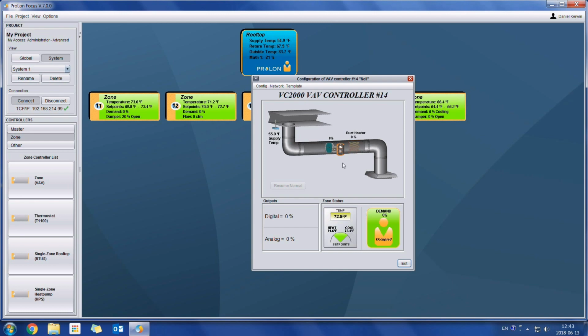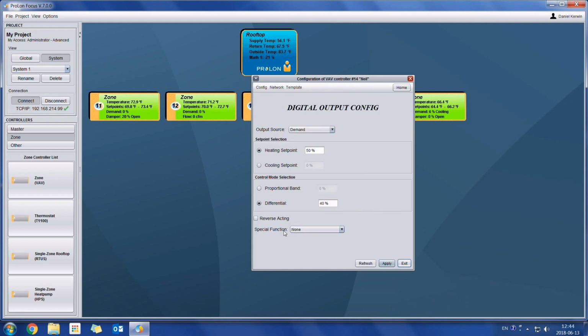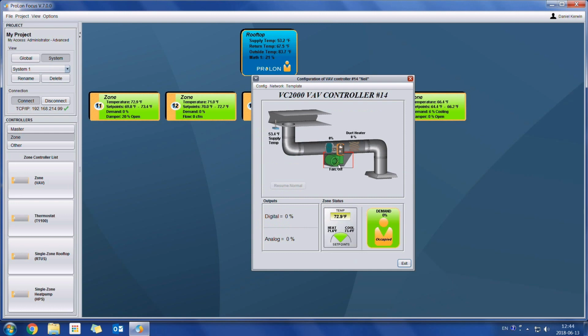Let's say I would like to add something else. Suppose we have a project where it's a fan powered VAV, so now I would like to control a fan with my digital output. So I could double click on the digital output, go to special function. Here we have fan powered box series or parallel, so it depends which configuration. So let's choose the parallel configuration, press apply, and now we have the fan graphic which has just popped up. If you right click on an element, you can override it from here.